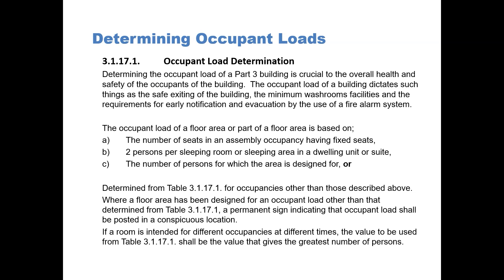Where a floor area has been designed for an occupant load other than that determined from Table 3.1.17.1, a permanent sign indicating that occupant load shall be posted in a conspicuous location within the room. If a room is intended for different occupancies at different times, the value to be used from Table 3.1.17.1 shall be the value that gives the greatest number of persons.